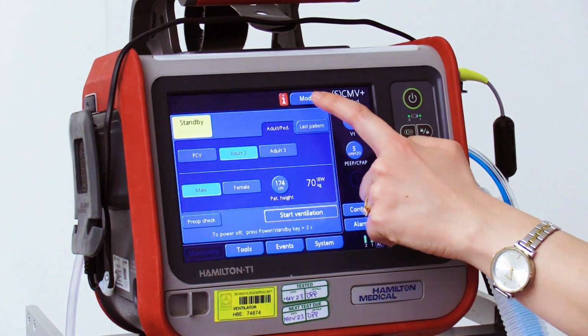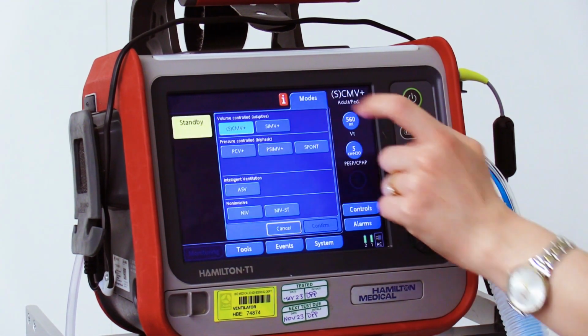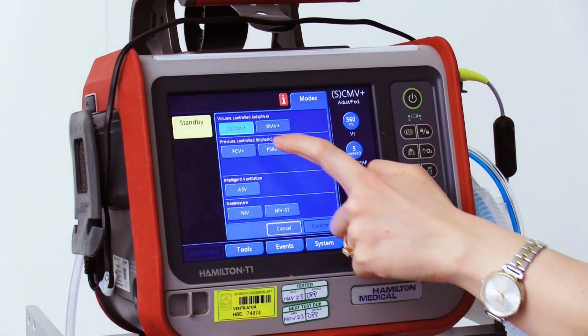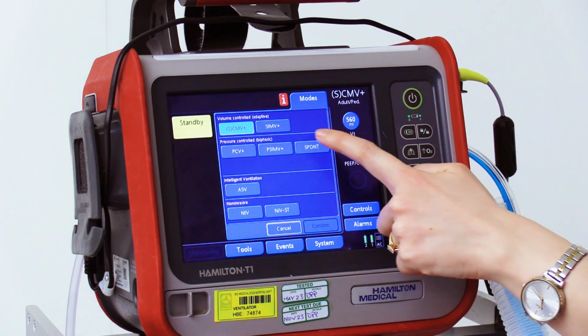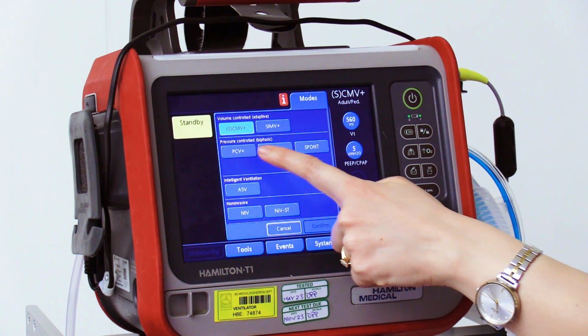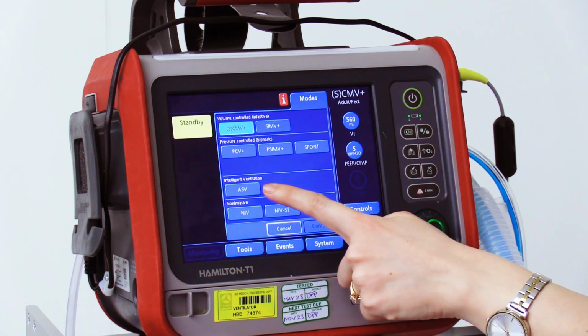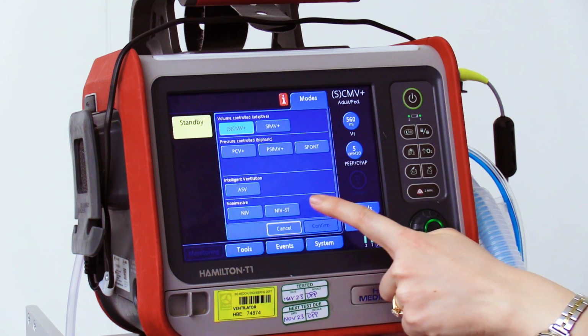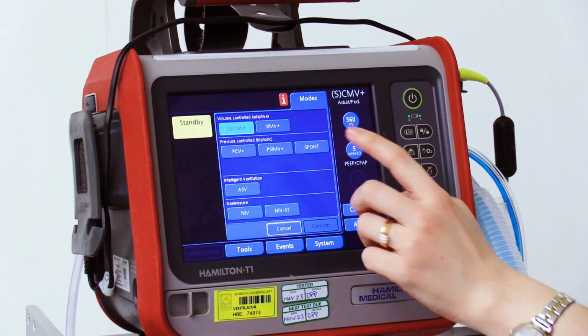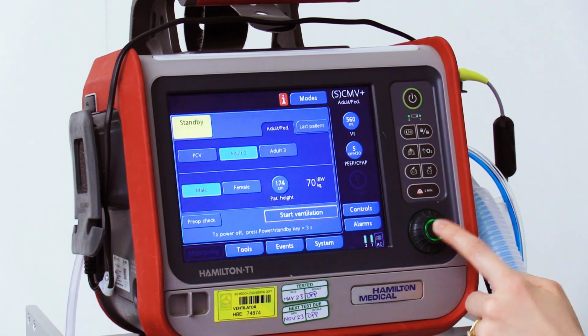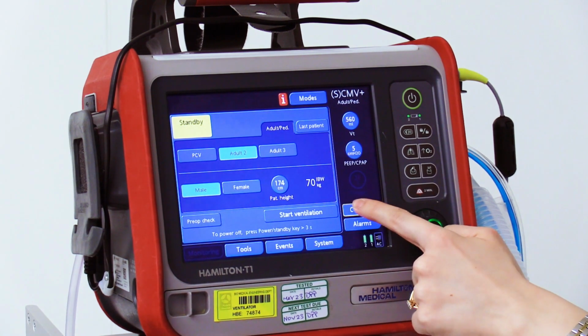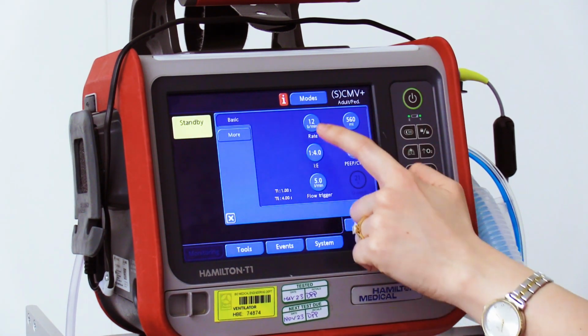Press the Modes button to access the ventilation modes. The T1 ventilator supports the following types of modes: volume-controlled mode, pressure-controlled mode, pressure support mode, intelligent ventilation mode with adaptive support ventilation, NIV, and high-flow oxygen therapy. Select and confirm the mode, and press the Control button to access the ventilation settings.